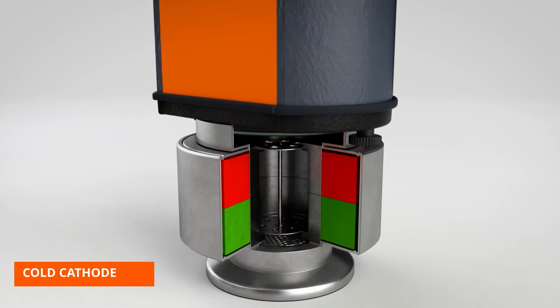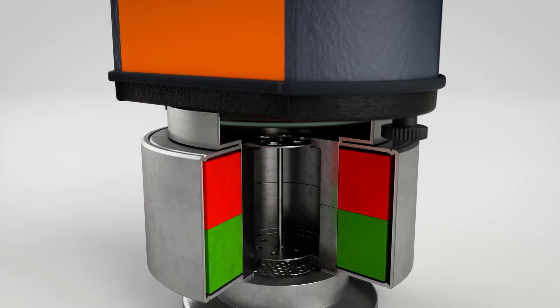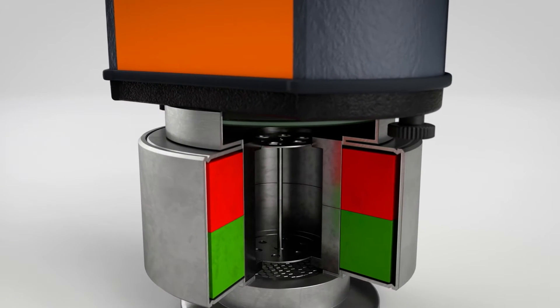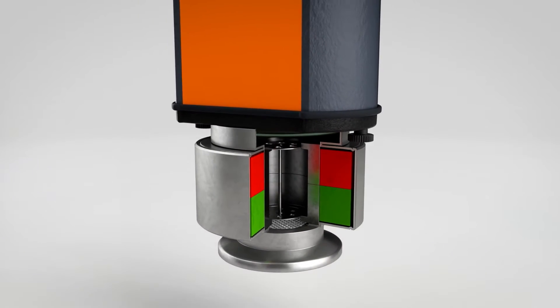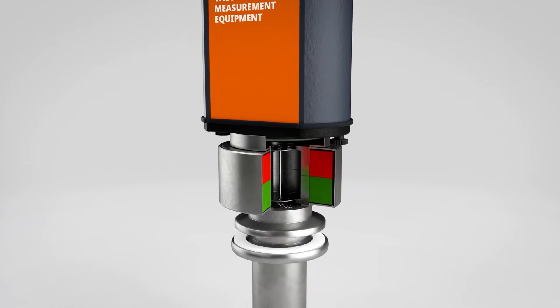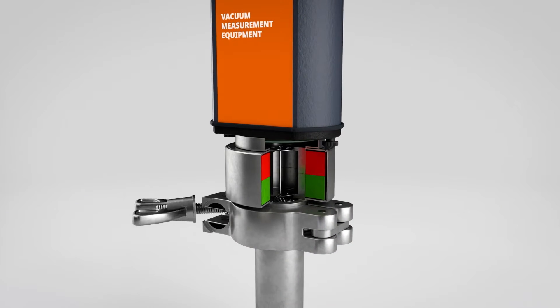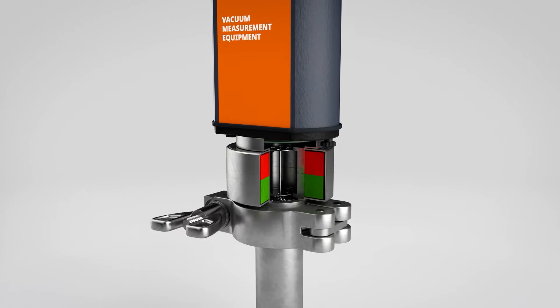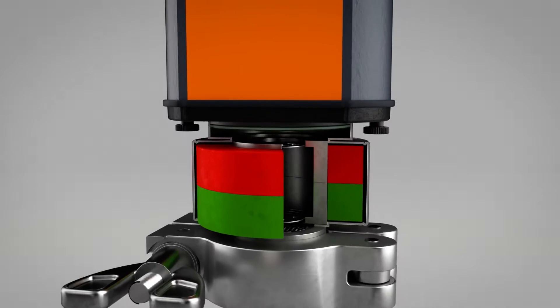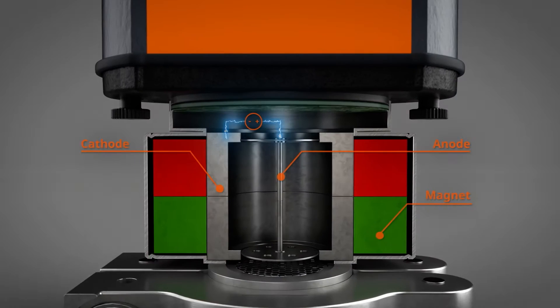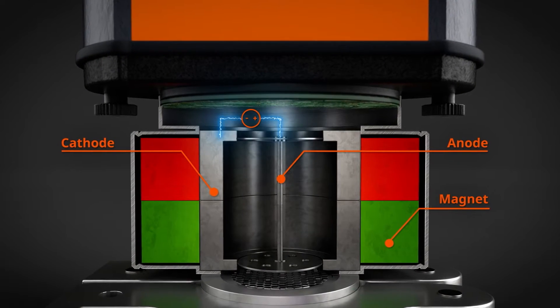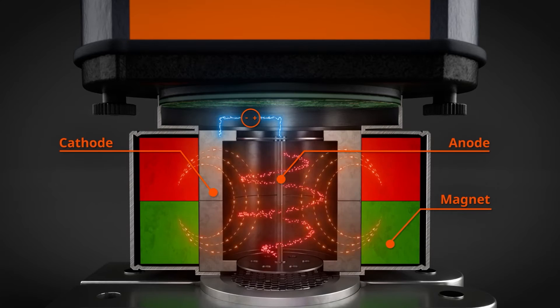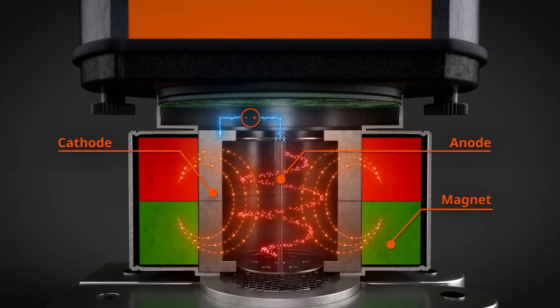A cold cathode gauge determines the pressure by measuring the ionization current caused by gas ions that collide with a low temperature cathode. The gauge consists of a cylindrical chamber surrounded by a magnet. Also present are two electrodes: the anode in the center of the chamber and the negatively charged cathode, which shields the magnet from the cylindrical chamber.